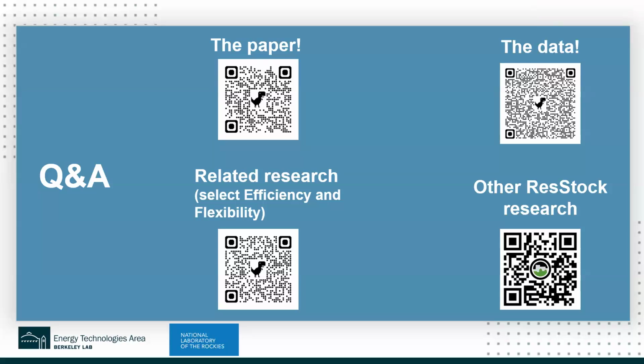I'll jump in with a quick follow-up. Agree with everything Lixie just said. There's a fun update in our new 2026 National Electrical Code: you're now explicitly allowed to deduct removed loads from your metered maximum demand if you're using that 0.87 method. So if you were, for example, removing an air conditioner and replacing it with some other technology, you'd be permitted to deduct that air conditioning load. That speaks a bit to what Lixie was describing. The 80% number is really meant to relate to continuous loads, so generally that 80% would only be relevant if every load on the panel was considered continuous, which is typically not the case. So, consult your electrician on that one.